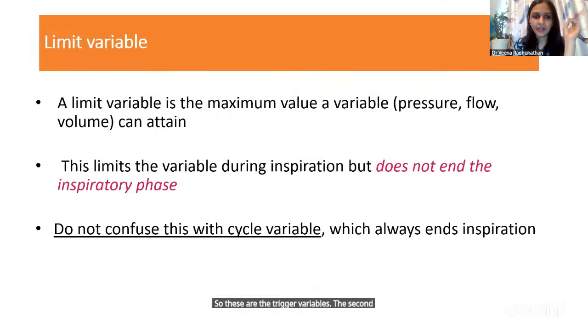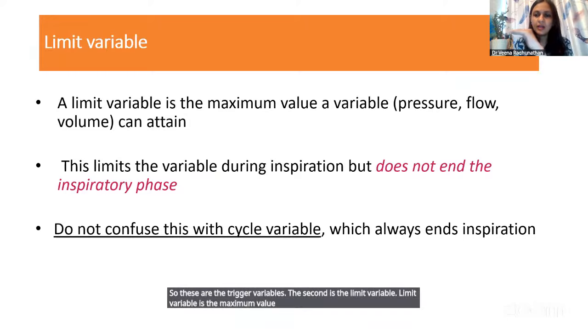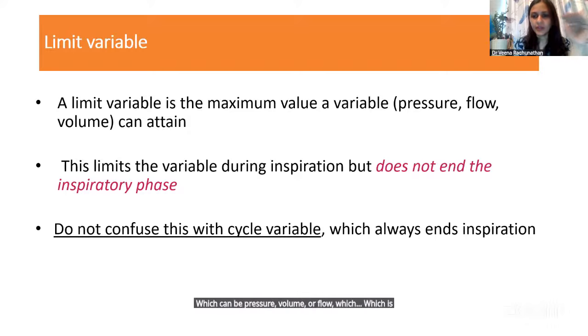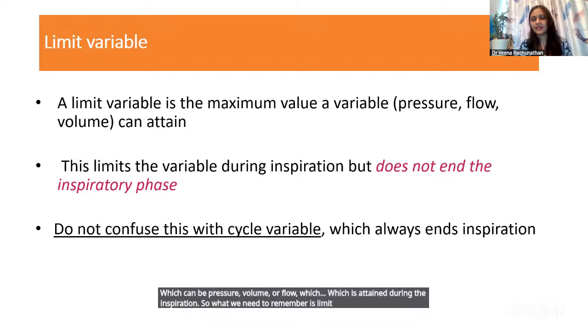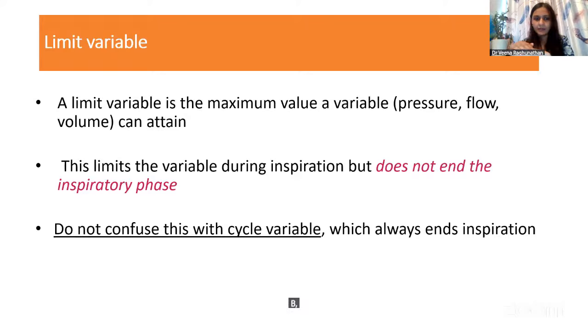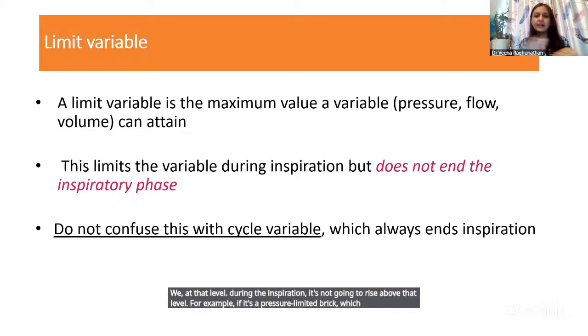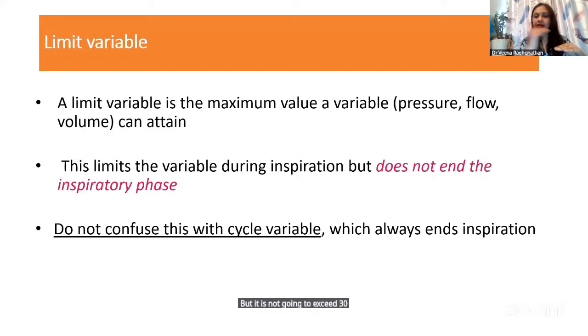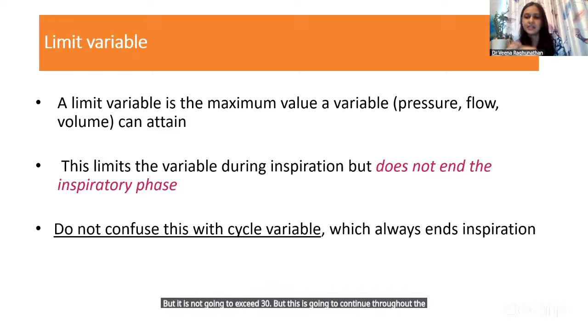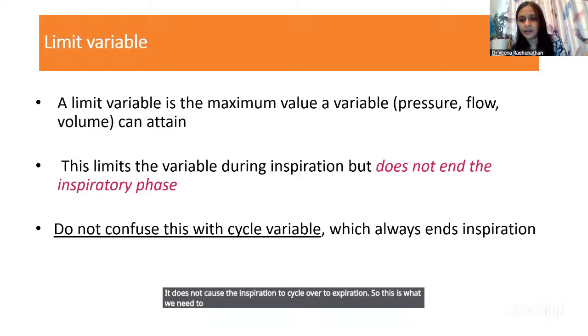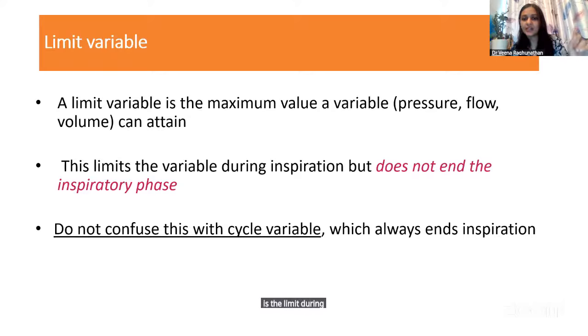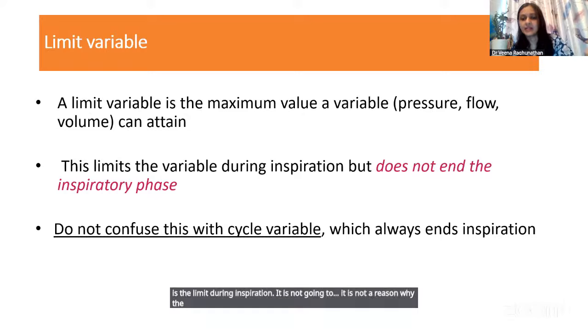The second is the limit variable. The limit variable is the maximum value of a variable, which can be pressure, volume, or flow, attained during the inspiration. What we need to remember is that the limit is something that is going to be at that level during the inspiration. It's not going to rise above that level. For example, if it's a pressure limited breath, which we set at 30, then the pressure delivered is going to be 30 during inspiration, but it is not going to exceed 30. This continues throughout the inspiratory phase. It does not cause the inspiration to cycle over to expiration. So a limit variable is the limit during inspiration. It is not the reason why the breath is cycled to expiration, because that is something different. That is the cycle variable.